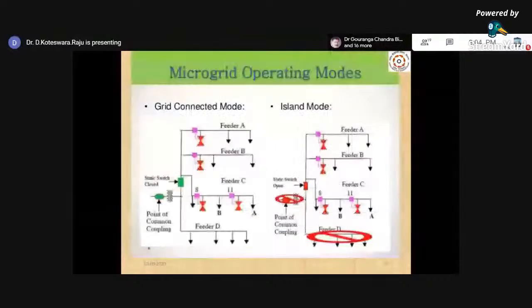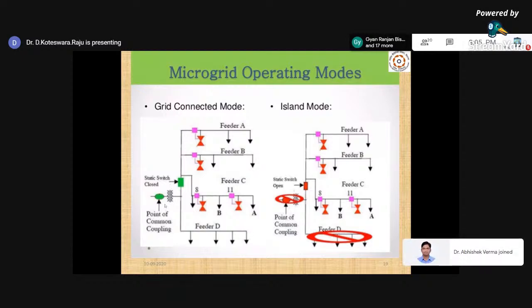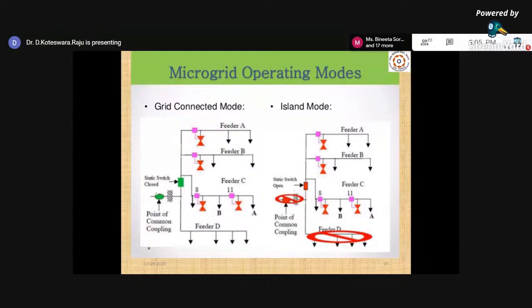This single line diagram clearly shows the properties of grid connected mode and island mode. There are different feeders: feeder A, feeder B, feeder C, and feeder D. Feeder A, B, C are served by the microgrid, and feeder D is served by the utility grid. So this microgrid is connected to the utility grid. Here I have not shown the utility grid, just the point of common coupling, where the microgrid connects to the utility grid through a static switch.